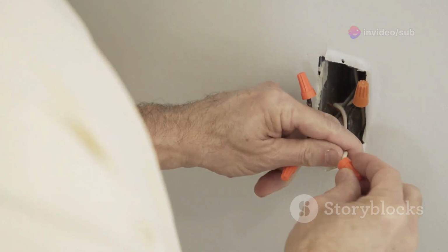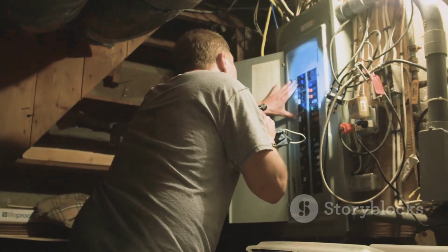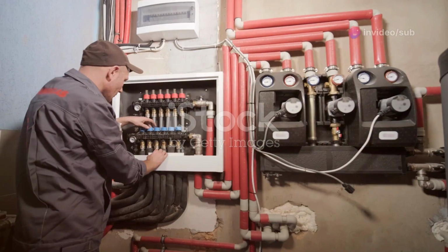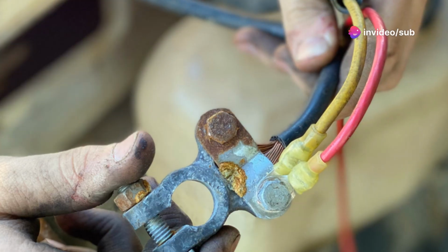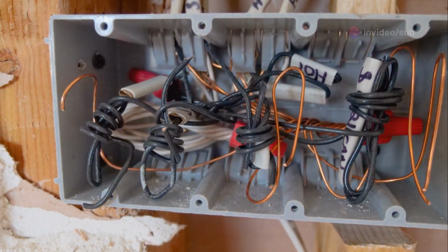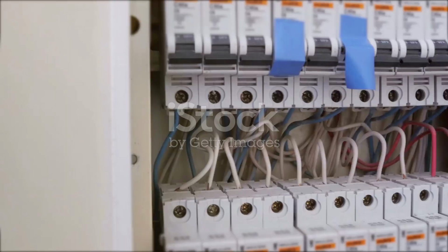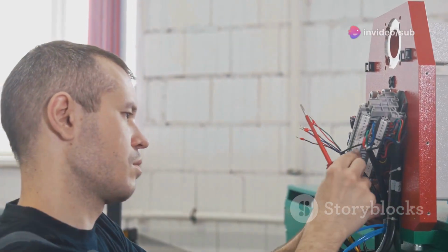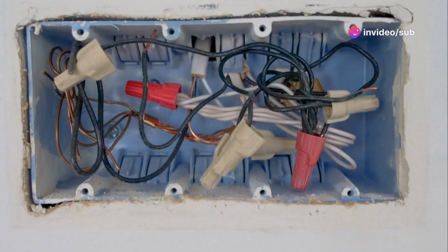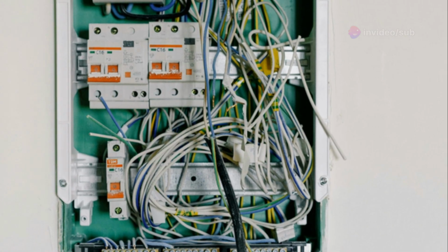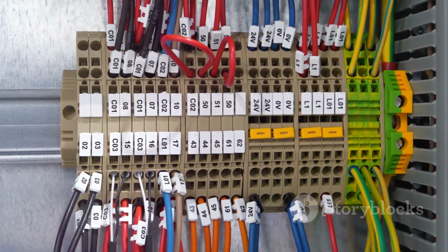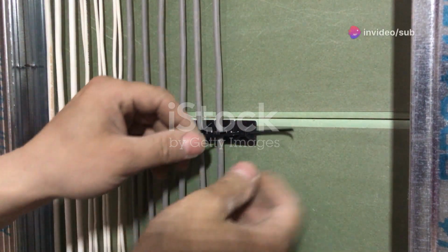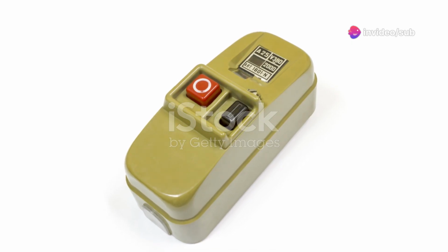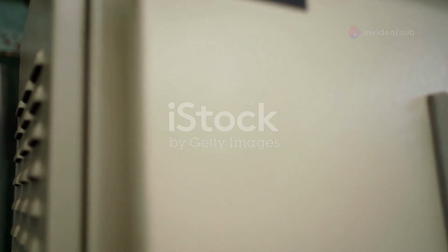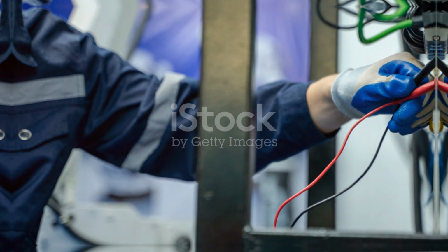Single-terminal breakers are the standard choice for most home circuits. They work well when you only need to connect one branch circuit per breaker. They're simple, reliable, and easy to inspect. Multi-terminal breakers shine in more complex setups. If you need to feed two circuits from one breaker or connect both a busbar and a wire, they make the job easier. This is common in commercial panels, sub-panels, or places where space is tight and wiring needs to be flexible. The downside: multi-terminal breakers can tempt people to overload them or to mix wire sizes. They require more care and attention to avoid mistakes. Always check the breaker's label to be sure you're wiring it the right way. Choose the type that fits your project and follow all guidelines for safe installation.